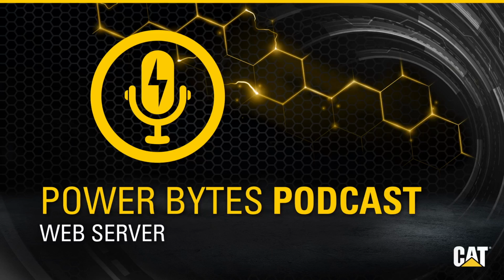So tell us about some of the benefits of connecting to the web server. You'll have access through the web viewing real-time parameters from your genset from the comfort of a remote location. Say you want to sit in your service truck, you want to be in an office, really as far as your cable can reach, you can sit. And this is particularly useful, as you do long duration burn-in testing or during commissioning of a genset. You'll be able to see if your genset is showing any events, warnings, or shutdowns, and know whether or not the genset's running. You get basic engine overview with items like your coolant temperature, oil pressure, and engine speed.